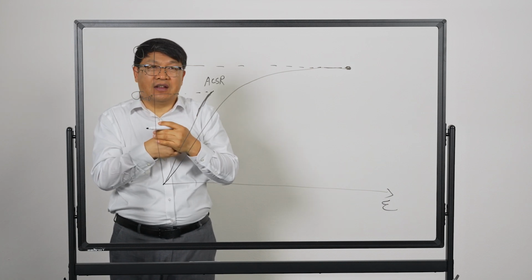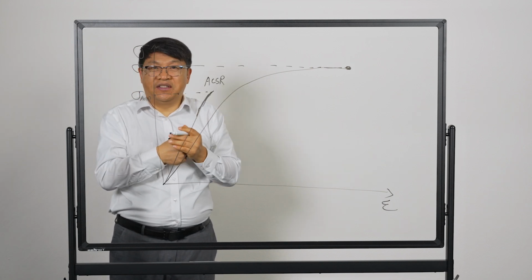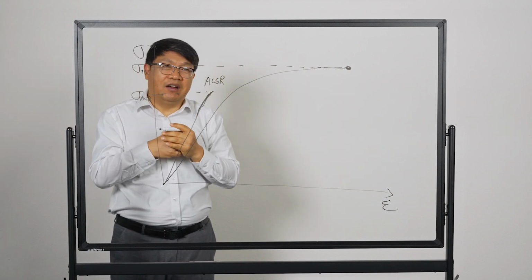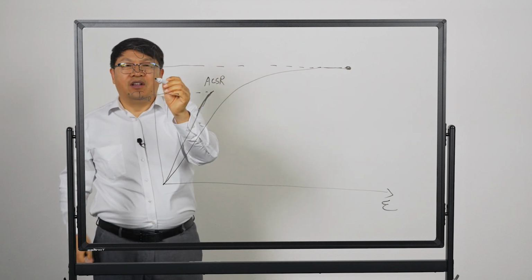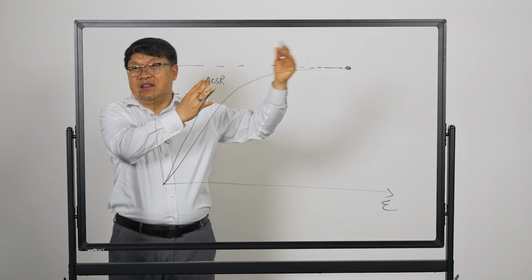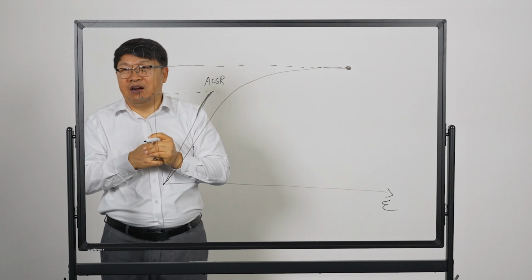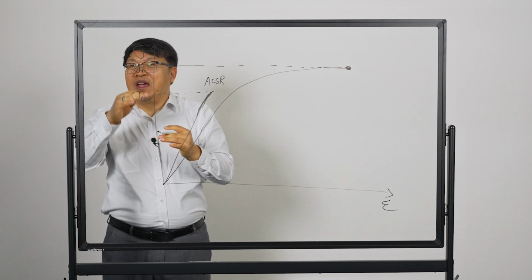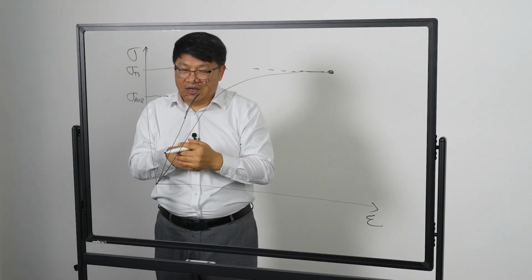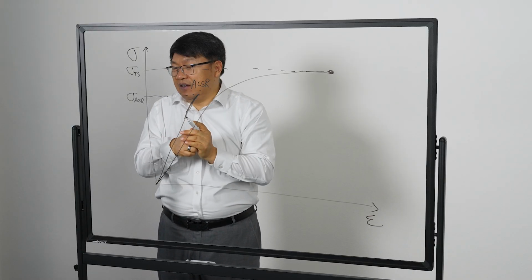Okay, in the TS conductor case, we normally have reserve strengths, like a 10 to 15% margin of safety. So between your actual strengths and your rated strengths, there is that margin. ACSR, you normally don't have that much of a margin. They've been around for all these years.